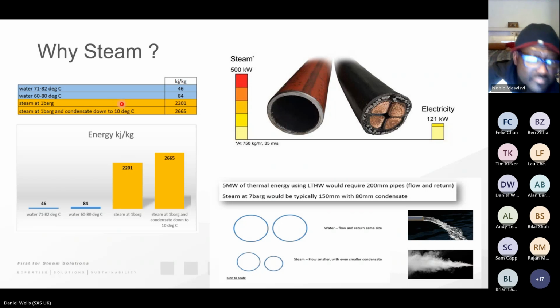The infrastructure, we've got to rip out thousands of meters of steam pipe and replace it with an equal distance of a much, much larger diameter water pipe. Might be asbestos clad, might be in a difficult to access area, might have to go to landfill. That's not going to be very carbon friendly.